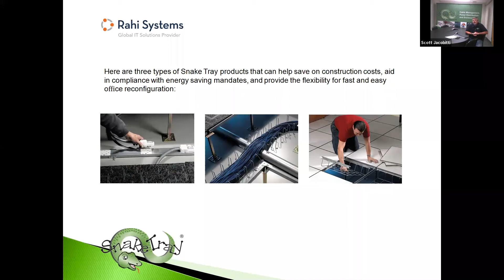The whole concept of the Snake Bus was to bring in a tremendous amount of power underneath that raised floor. We're looking at a 50 amp 3-phase circuit, which has an availability of about 18,000 watts of power. That is far more than any of the other traditional spider systems that might be out there delivering power for the raised floor, which in turn gives us a tremendous amount of flexibility in the way that we locate people within the space. So if we have to move people around, we're always going to have available power.